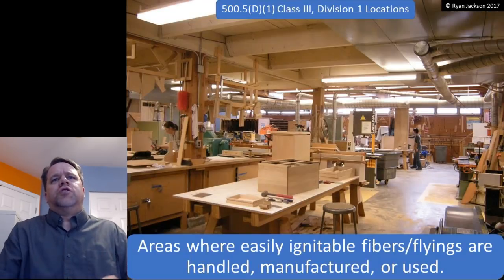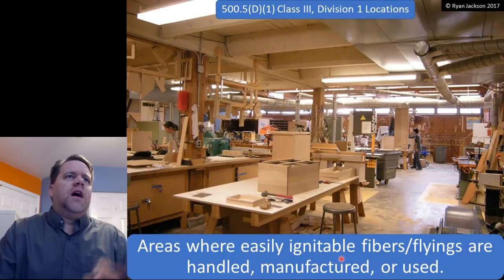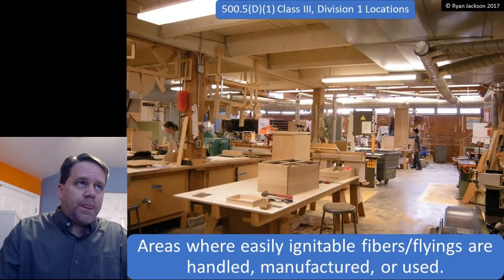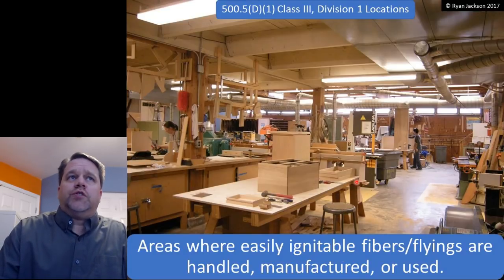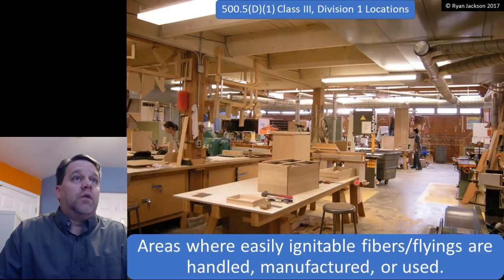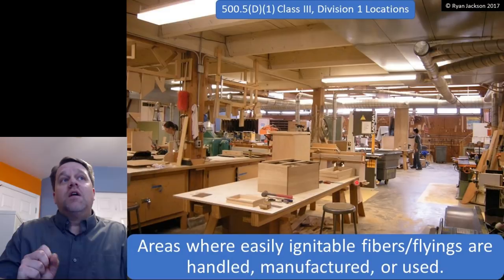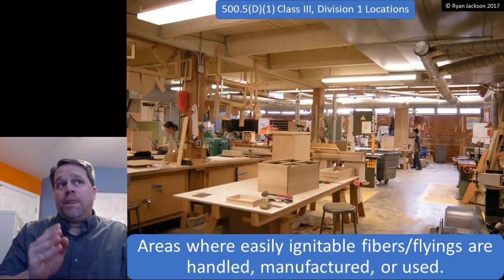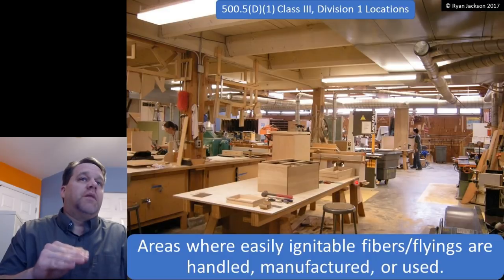So here in this wood shop, and don't read this quite yet, let's just talk about it first. There are areas in this wood shop that could very well be a Class 2 location where we have combustible dust. I would say anywhere near sanding operations is probably Class 2 because you have combustible dust.